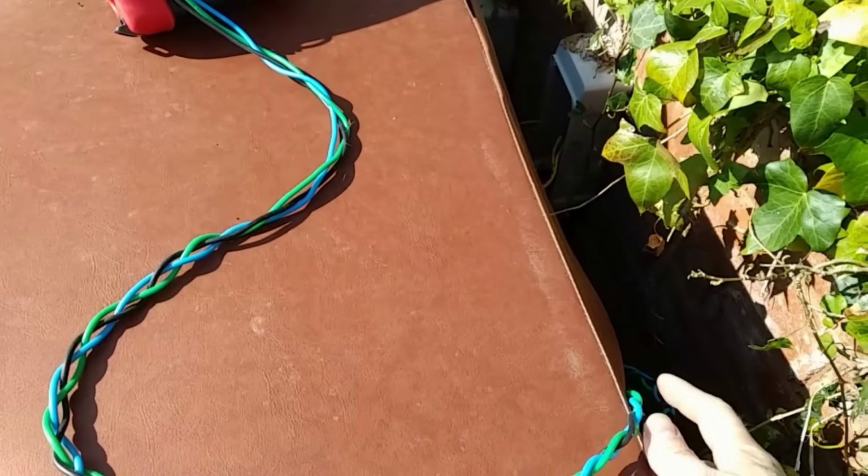Oh boy. Just gave the game away, just turned around and there it was. There's our SY cable. Partially buried, partially surface run. Obviously linking that socket to that socket. All this cabling's a bit undersized really for the job, and if we have a look at this cable here, which is part of the armoured linking the hot tub to the sockets, I believe we can see on there it's stamped as 2.5mm and it's got a date of 2016, which suggests that all this is not very old.